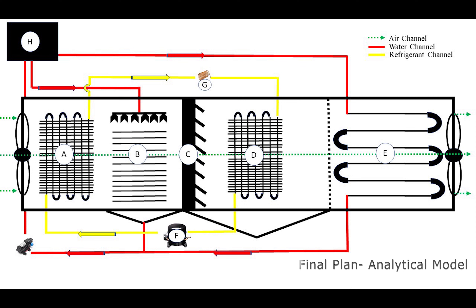This highly humid air passes through the evaporator to yield desalinated water while undergoing dehumidification. The dehumidified air is then reheated by the hot water flow to achieve comfort conditions before the first draft fan takes the air to the space to be conditioned.